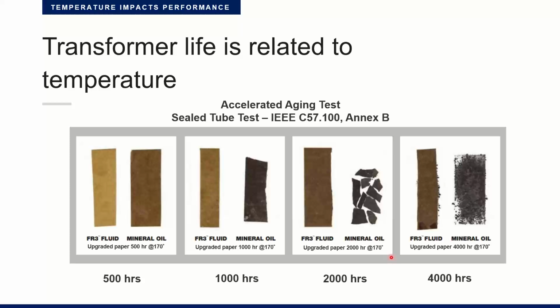So let's have a look at the test from the IEEE, which you see on this slide. So just imagine this is the paper in the area of the hotspot. You see at 170 degrees Celsius, and after 500 hours, the paper in mineral oil has already changed its color. FR3 fluid is still good. So then if you go to 1000 hours, the paper in the mineral oil has already lost its insulation. So the IEC says also when the paper has lost 65% of its tensile strength, this is the end of life of the insulation and also the end of life of the transformer. If you look at 2000 hours, the paper is destroyed. 4000 hours, it's just powder.